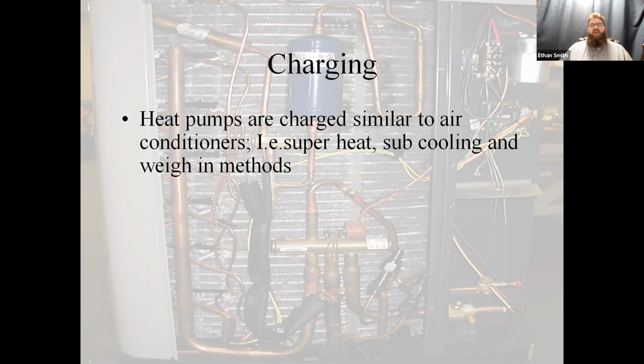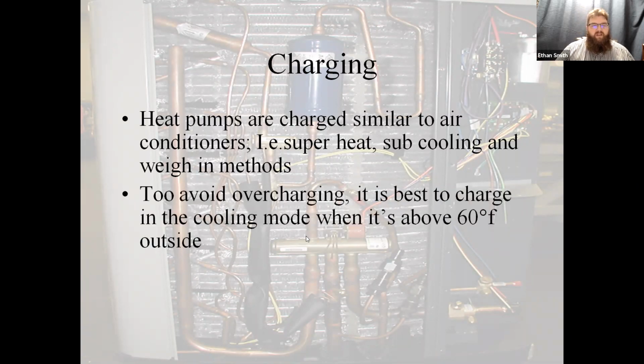We're going to charge them to a subcooling target these days because we're using all TXVs. It is critical that you get that subcooling correct. So you're going to look for that subcooling target on the outdoor unit. I will tell you guys, if you're going to err on the side of anything on that superheat or on that subcooling target, it's usually going to say plus or minus 2 or 3. I would say you err on the minus side of that with heat pumps. I don't go over my subcooling target ever on a heat pump charge when I'm charging in cooling. That being said, it is best to charge the unit in cooling mode when it's above 60 degrees outdoor temperature. The reason for that is charging during heating mode is always a bit of a guess.